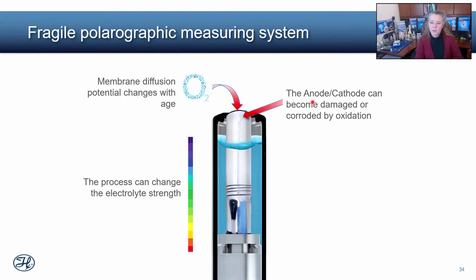Next, the anode and the cathode can become damaged or corroded by oxidation. It's a redox reaction. Naturally, these do get used up over time. You can replace the anode and cathode in some manufacturers' polarographic probes, but not all. These probes are actually considered consumables. If not the whole probe, definitely the components of the probe. But as those anode and cathode change in shape, in health, it will affect the ability for these to take consistent good measurements. There are some maintenance things you can do to compensate for that, and we'll talk about that in a minute.